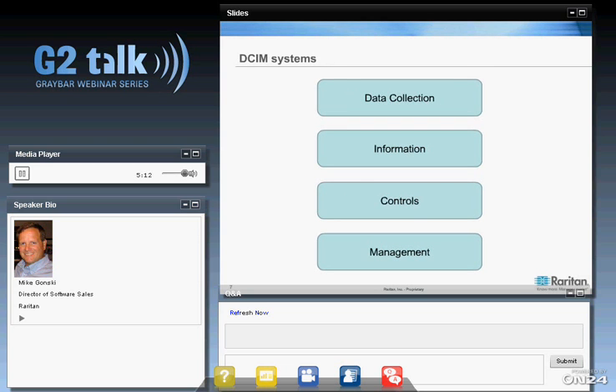Moving on to data collection: that might be a plug-in architecture supporting SNMP, with data like amps, volts, power factor, watts, kilowatt hours, temperature, and humidity. We're looking for high scalability. Information from DCIM systems includes dashboards, chargeback reports, capacity forecasts, gauges for capacity, and thermal analysis. Controls include the ability to cycle power outlets, do agentless graceful shutdown, or set power sequence for when power is restored or delayed. On the management side: firmware and configuration management, outlet and sensor label naming, and event notification.